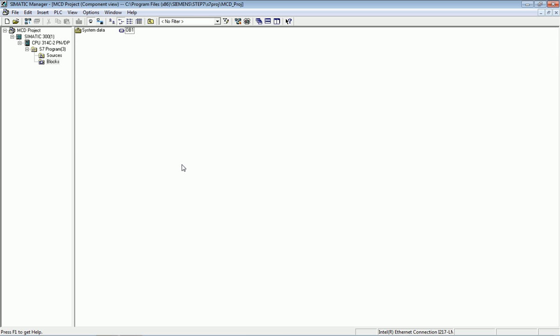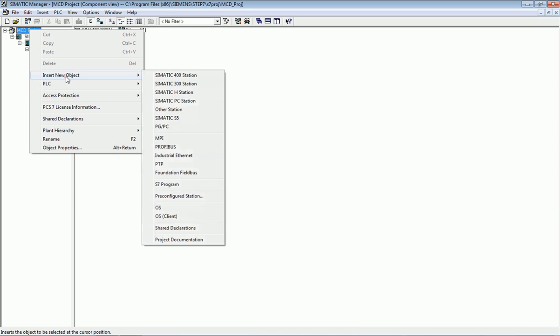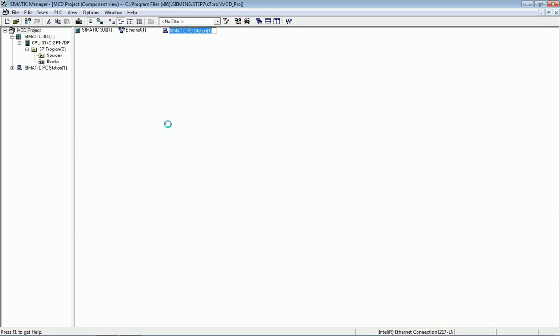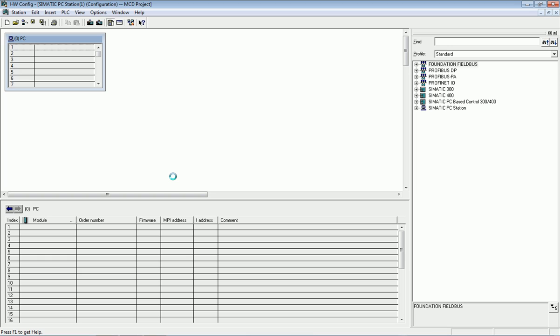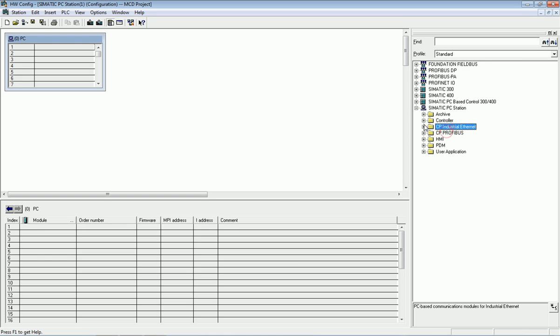After making the PLC configuration, we will go for OPC server configuration. First, I will select the project, right-click and insert a new object, then select PC Station because we are downloading the OPC server application to this PC. We open the PC station and go for configuration. In this window we will select Industrial Ethernet port, as the system is configured with an Industrial Ethernet port.